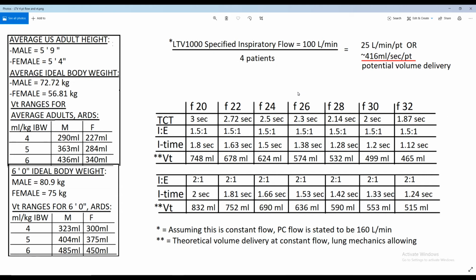Again, this is just trying to figure out, could this vent push that much volume in the amount of time that we're giving it? The amount of time being our inspiratory time, which would be a function of our cycle time, and of course our rate that we set on the ventilator. So looking at our numbers over here, I know this is getting a little confusing. I'm trying to make it as straightforward as I can.